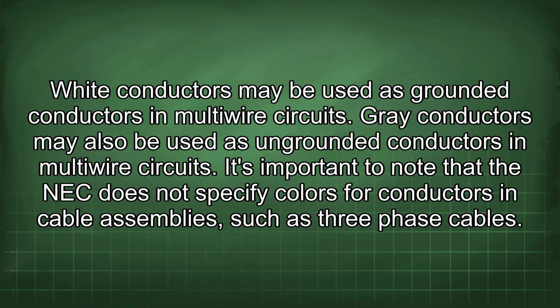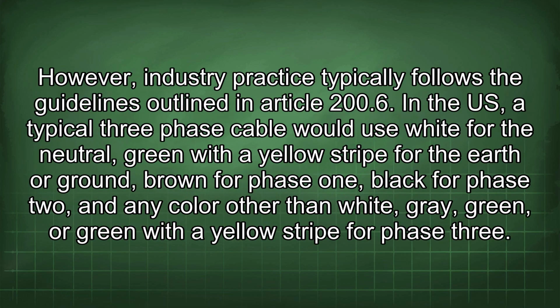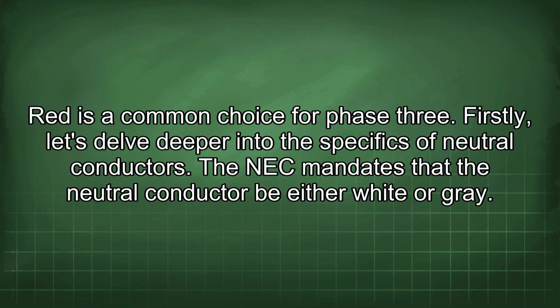It's important to note that the NEC does not specify colors for conductors in cable assemblies such as 3-phase cables. However, industry practice typically follows the guidelines outlined in Article 200.6. In the US, a typical 3-phase cable would use white for the neutral, green with a yellow stripe for the earth or ground, brown for phase 1, black for phase 2, and any color other than white, gray, green, or green with a yellow stripe for phase 3. Red is a common choice for phase 3.